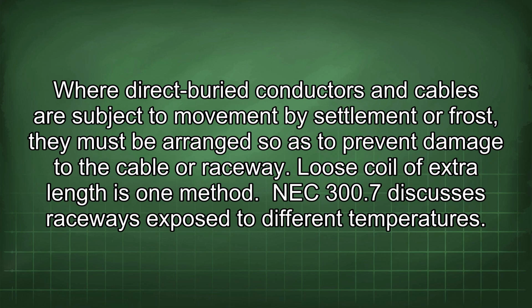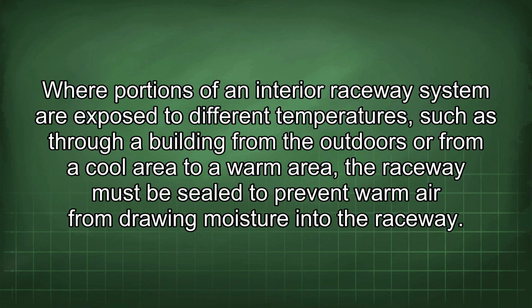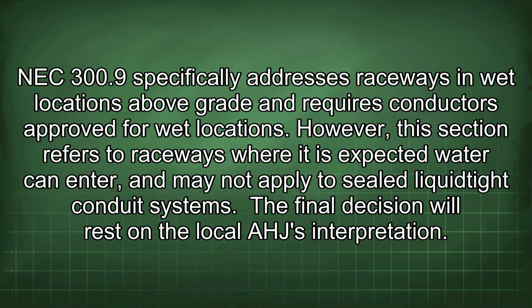NEC 300.7 discusses raceways exposed to different temperatures. Where portions of an interior raceway system are exposed to different temperatures, such as through a building from the outdoors or from a cool area to a warm area, the raceway must be sealed to prevent warm air from drawing moisture into the raceway. NEC 300.9 specifically addresses raceways in wet locations above grade and requires conductors approved for wet locations. However, this section refers to raceways where it is expected water can enter, and may not apply to sealed Liquidtight conduit systems. Final decision will rest on the local AHJ interpretation.